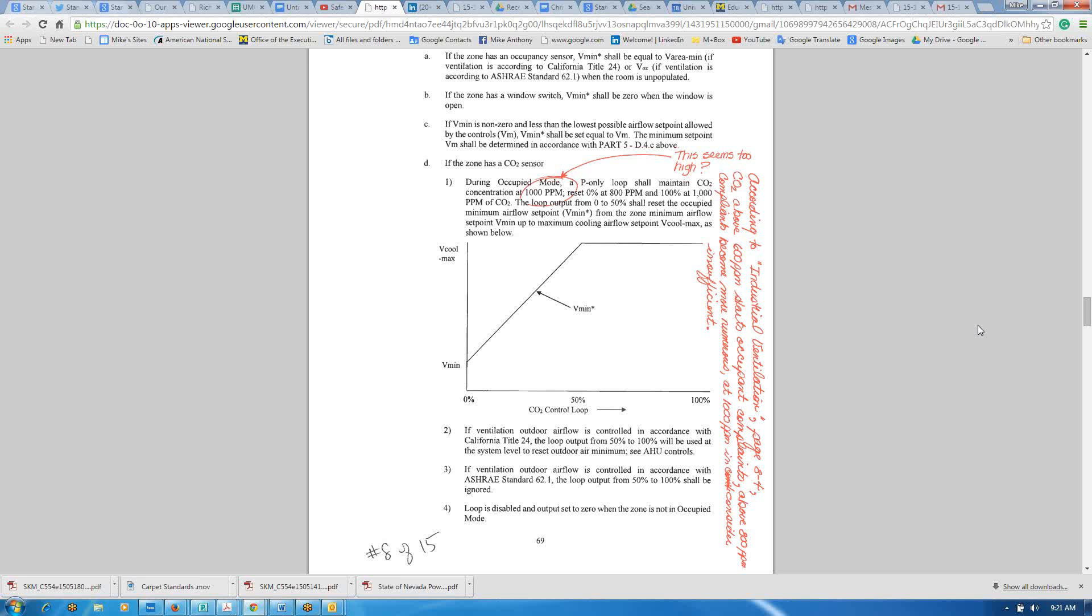I just question if the 1,000 is too high as a set point or something to maintain. But what makes it difficult to figure out is if you have 400 parts per million of outside air to begin with, in order to keep it in that 700 or 800 parts per million range, you might require more outside air, depending on what your occupants are doing. I think on this one, it might be a semantics thing. Instead of saying shall maintain CO2 concentration, maybe it should be shall limit CO2 concentrations or control below 1,000 parts per million. In other words, at 1,000 parts per million, you're at 100% open on your dampers. At 800, they're saying that you start opening the dampers at 800, so you're going to fall somewhere in between the two. But it kind of sounds like you're shooting for 1,000, and really that's not what they're trying to do. You may want to word that and say something like shall not keep it from exceeding 1,000 parts per minute.